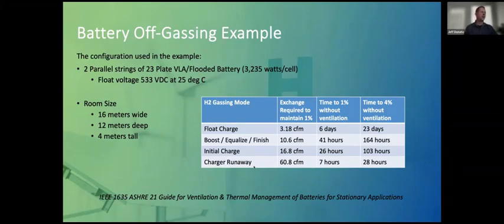So in each of these scenarios with this battery, the calculations prove that for this size of room and this type of battery, I need 3.18 CFM of airflow in that room. As soon as I go into boost charging, you can see I now need 10.6 CFM. And again, if I'm doing an initial charge, which is a little higher charge, 16.8 CFM. And then if the charger goes into a malfunction state and ramps up into maximum charge voltage, then I'll need a whopping 60.8 CFM.